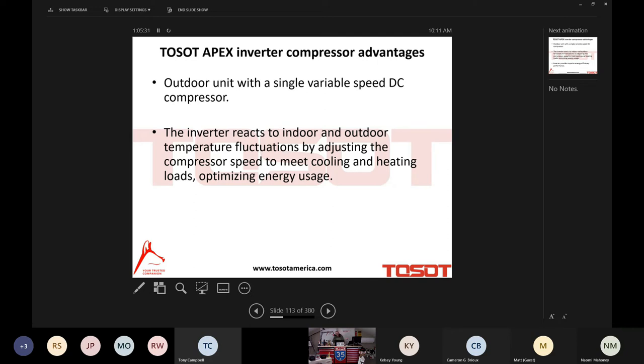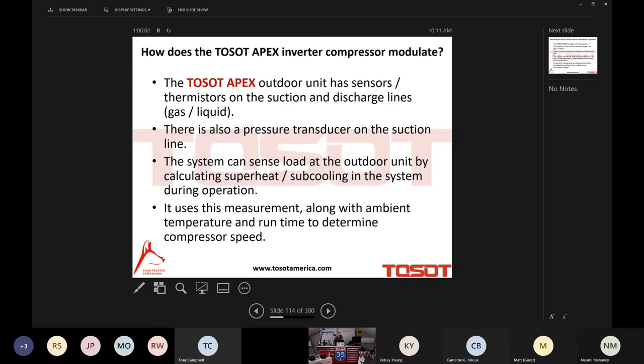Now, having said that, it's a little bit more complicated in the Apex world because there's less communication between the indoor and outdoor unit than there is on a Tosot mini split system, right? There's less modulation going on, but modulation nonetheless. And it is the inverter compressor that, again, provides these crazy efficiencies. In the Apex world, 20 SEER. Again, nothing to sneeze at, in my opinion.